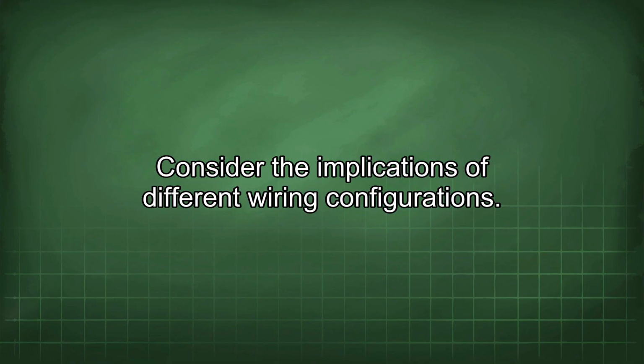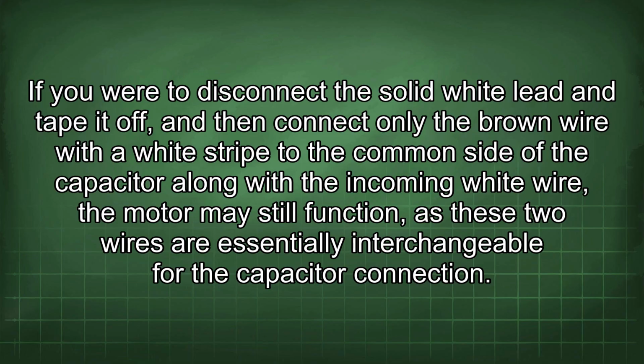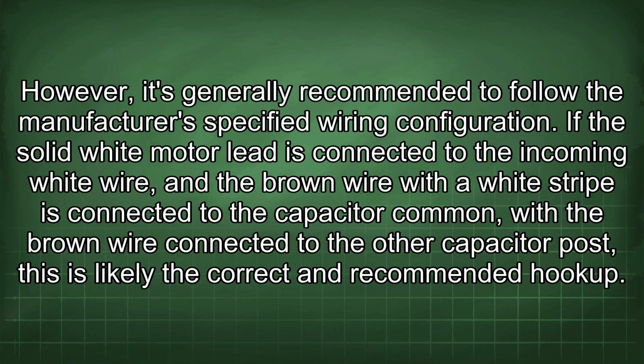Consider the implications of different wiring configurations. If you were to disconnect the solid white lead and tape it off, and then connect only the brown wire with the white stripe to the common side of the capacitor along with the incoming white wire, the motor may still function, as these two wires are essentially interchangeable for the capacitor connection. However, it's generally recommended to follow the manufacturer's specified wiring configuration.